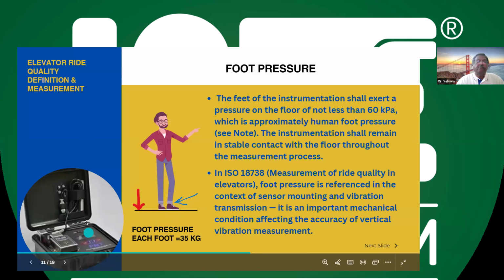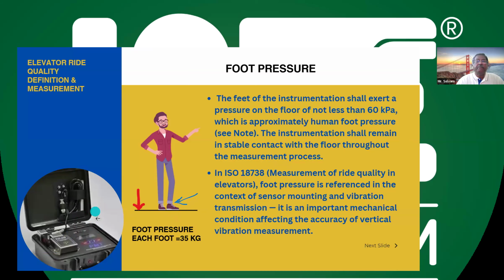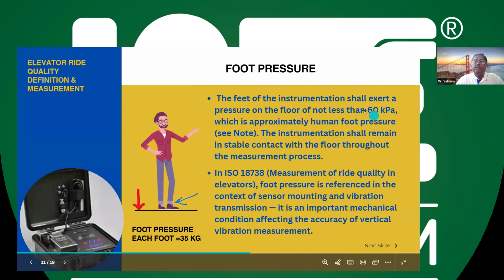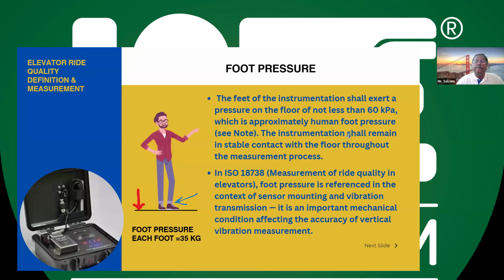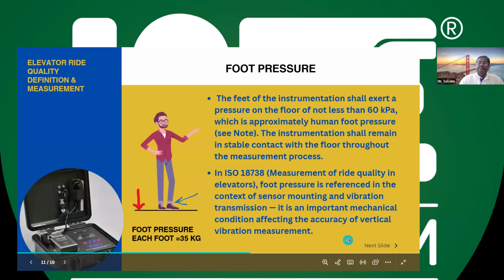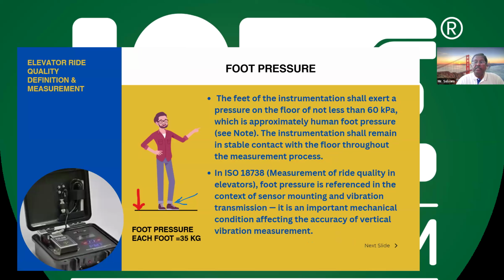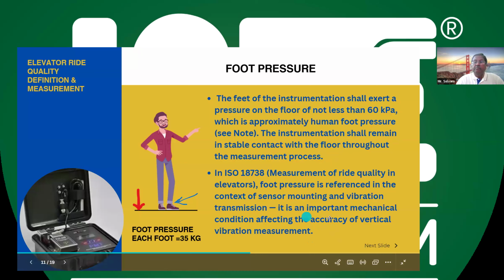So it necessarily has to have some self weight. For example, in this type of tool, the PMD tool, the self weight is around 5 kg. It is intentionally kept at that weight so that it can meet the standards given by ISO 8041, and now the latest 8100 also. The idea is that the instrumentation shall remain in stable contact with the floor throughout the measurement process. So the sensor has to be stable when measuring. If it has no contact with the floor, it cannot sense the floor. So it is an important mechanical condition affecting the accuracy of the vertical vibration measurement.